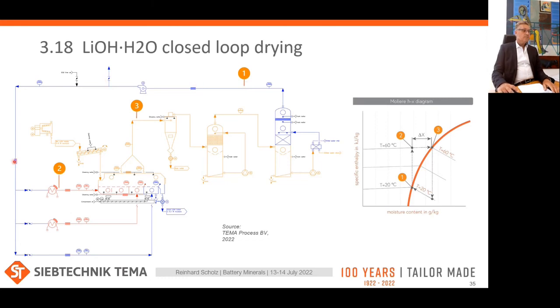The airflow is heated in the heater, at constant moisture level, to a temperature of, for instance, 60 degrees, point 2 to 3. The heated air can now absorb the moisture from the fluidized bed. The higher the temperature becomes, the larger this drying potential delta X becomes. If we would increase temperature to here, the delta X would be much larger. After the normal air treatment to get rid of the dust here, which I just explained, the air is cooled to 20 degrees by means of chilled water. It's from here to here.